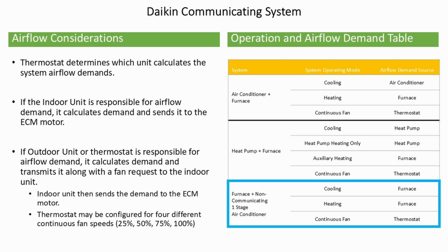If the system is a furnace and a non-communicating single-stage air conditioner, if the system operating mode is in cooling, the airflow demand source is the furnace. If the system operating mode is in heating, the airflow demand source is the furnace. If the system operating mode is in continuous fan and there is no current call for heating or cooling, the airflow demand source is the thermostat.